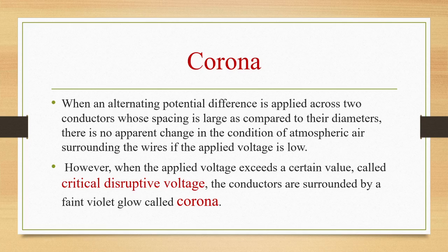Whenever a voltage higher than the critical voltage is applied between two parallel polished wires, the glow will be quite even. After operation for a short time, reddish beads or tufts form along the wire, while around the surface of the wire there is a bluish white glow. If the conductors are examined through a stroboscope so that one wire is always seen at a given half of the wave, reddish tufts or beads are formed when the conductor is negative and a smoother bluish white glow when the conductor is positive. The AC corona viewed through a stroboscope has the same appearance as direct current corona.